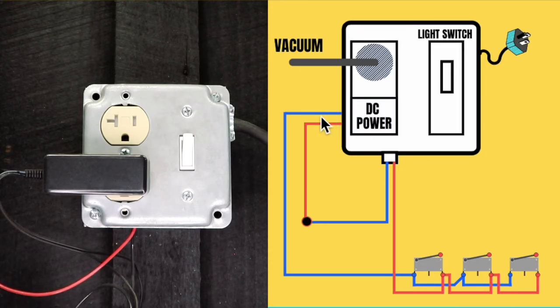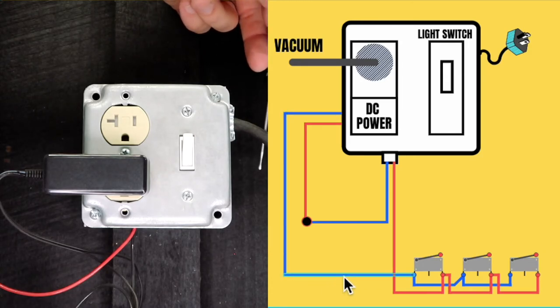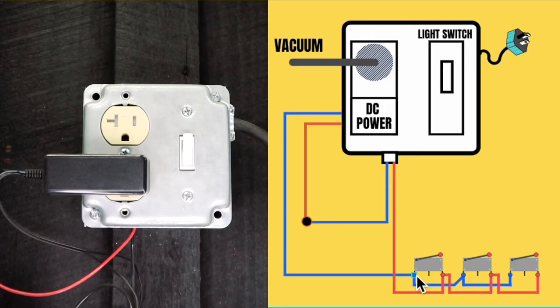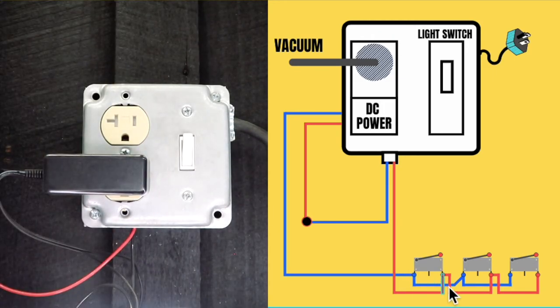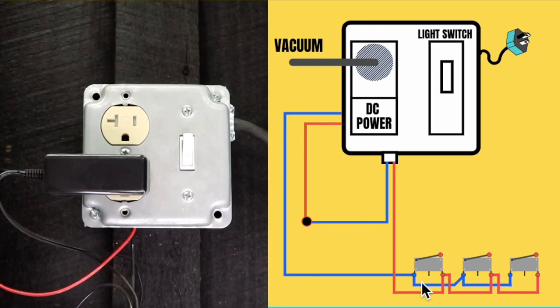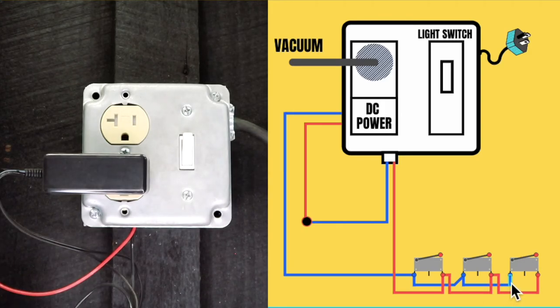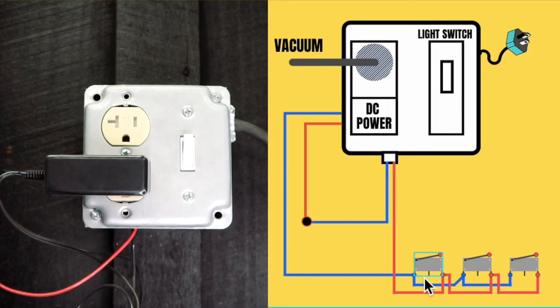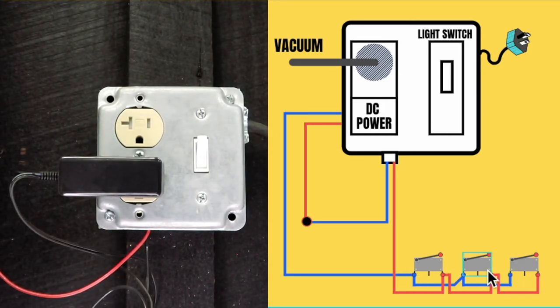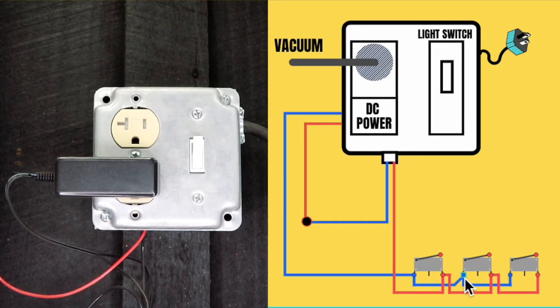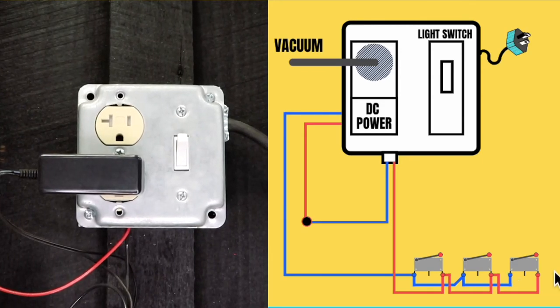So in the lower plug, you want to put your DC power and you've got your blue wire, which goes directly to your micro limit switch, the first tab. So this would be your neutral. Okay. And then you're going to jump that blue wire to the first tab of your next micro limit switch. Now this length right here can be a hundred feet. It could be a thousand feet. It doesn't matter how many feet it is. As long as you go from the first, your neutral right here to the neutral right here on your next outlet. And then same. Likewise, I only put three on here for the sake of space, but my blast gate system has, I think, 12. So this is three. You can do the exact same thing with a hundred micro limit switches. It's just follow this pattern. Look at this pattern. So it's your neutral goes to the front, jumps to the front, jumps to the front. Okay. And jumps to the front, jumps to the front and it keeps going.